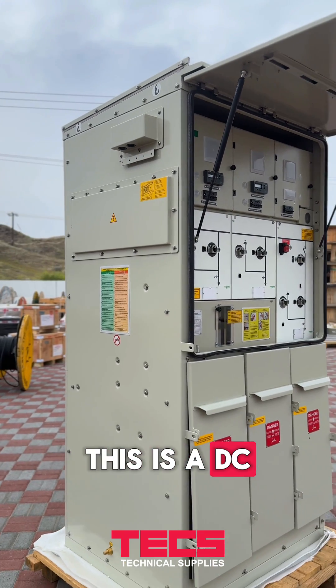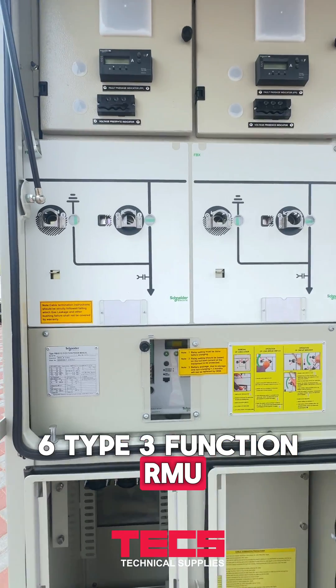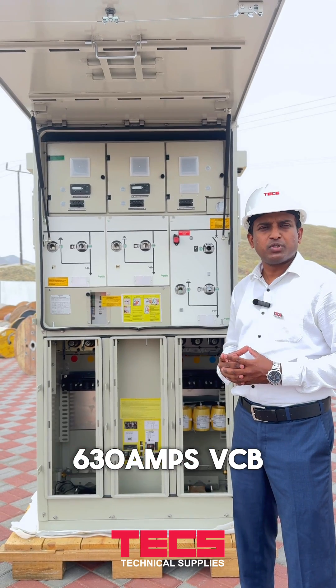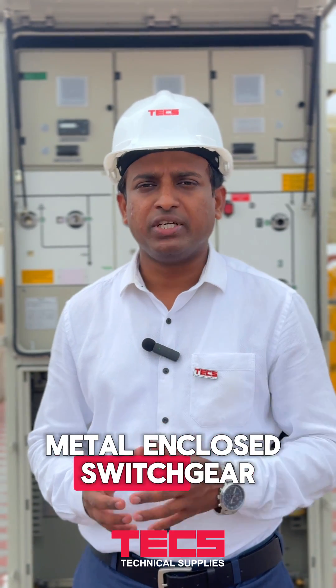This is a DCRP approved RMU. It is a SF6 type 3-function RMU, a combination of 2 switches and 1 circuit breaker. The protection to the transformer is provided by a 630A VCB with the help of self-powered relay DPX V5. It is a complete factory assembled metal enclosed switchgear.